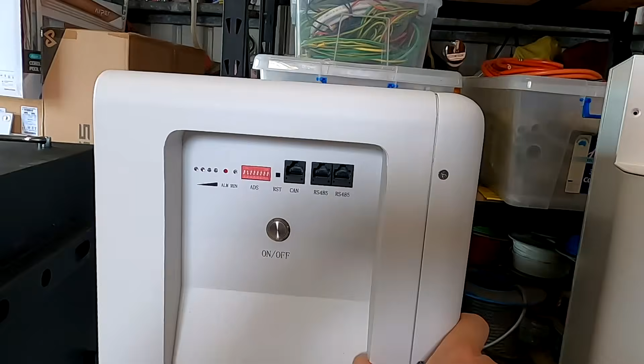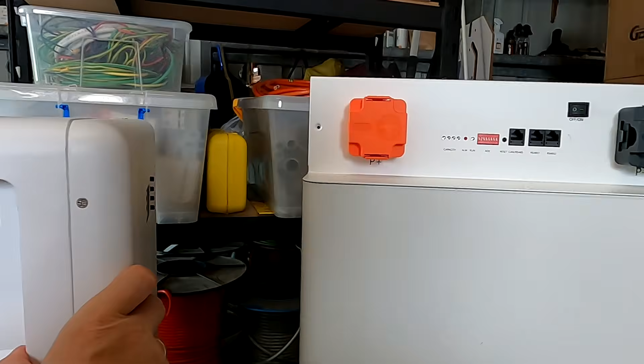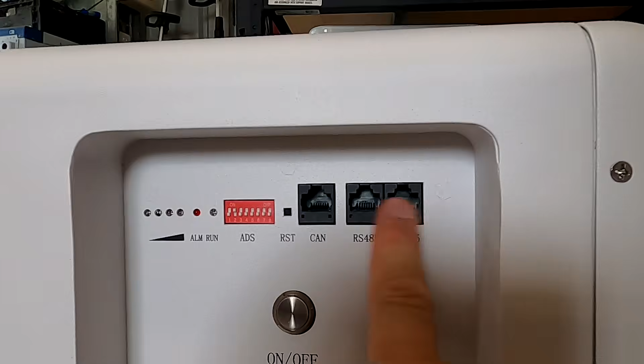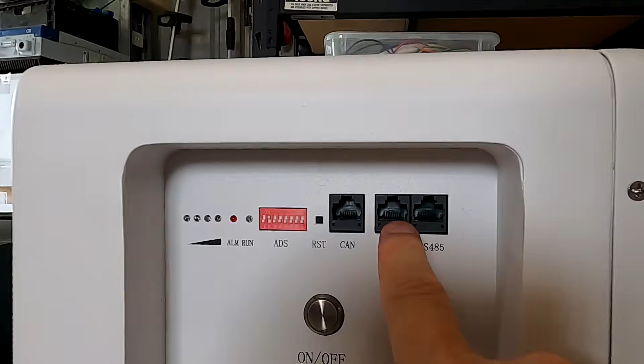The EEL battery and the Seplos battery both have Seplos BMSs built in, and they only come with 1 CAN port for your inverter and 2 RS-485 ports for internal communication and computer programming. So if you want to program one of these BMSs, you have to disconnect one of the ports, breaking the chain of communication, which could lead to a total system shutdown because the BMS loses connection to one of your batteries, and as a precaution it may shut down your whole system.